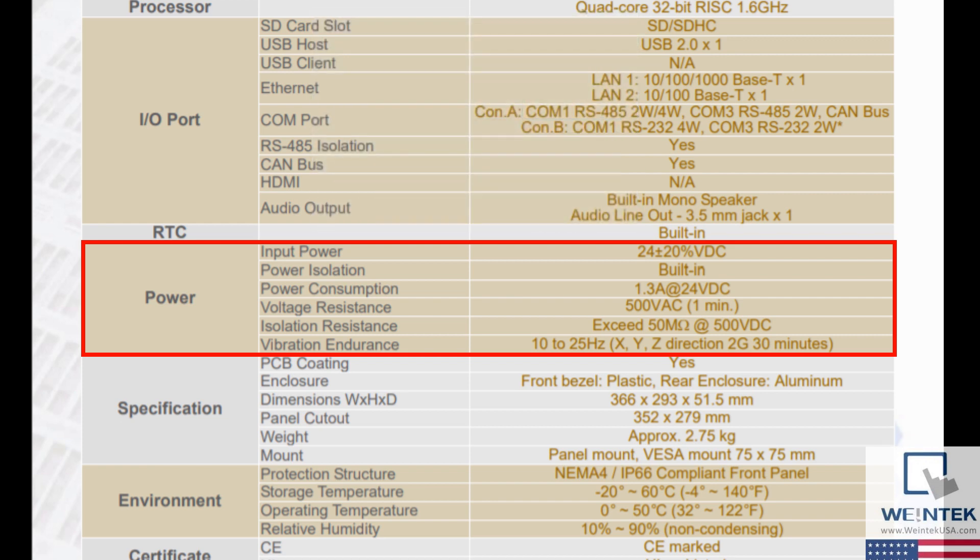Power isolation is a protective feature that provides electrical separation between two circuits. This barrier ensures that electrical equipment is safe and prevents shocks or fire hazards. Power consumption is the energy needed for the device to function, which is 1.3A at 24V direct current. The voltage resistance section denotes that the screen has been tested for and can withstand 500V of alternating current for one minute.